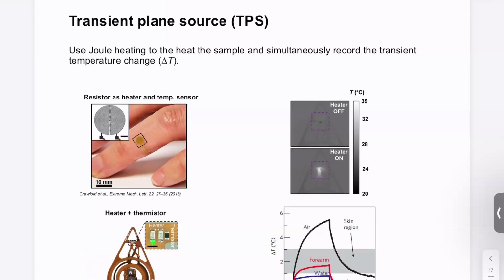So we see it uses two resistors as the heater. You apply voltage to a resistor, then it generates heat. Then next to the heaters, you have thermistor that measures temperature, right? This is the thermistor we were just talking about. So what this device is doing is that it's going to apply some heat by the resistors, and at the same time, the thermistor monitors temperature change.